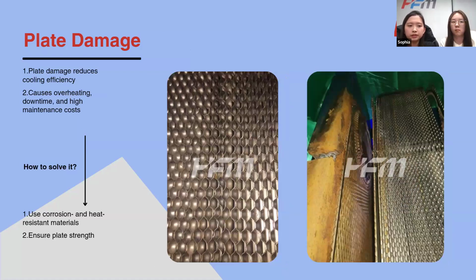So the last problem is plate damage. Plate damage is usually due to mechanical collision, corrosion, or overloaded operation, and the plate may be damaged, which may result in leakage, performance degradation, or the need to replace parts. So it is important to focus on the selection of corrosion resistant, high temperature and high pressure resistant materials, and consideration of plate strength design, so that we can solve it.